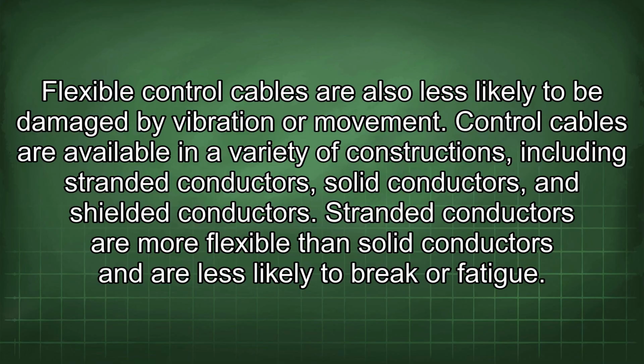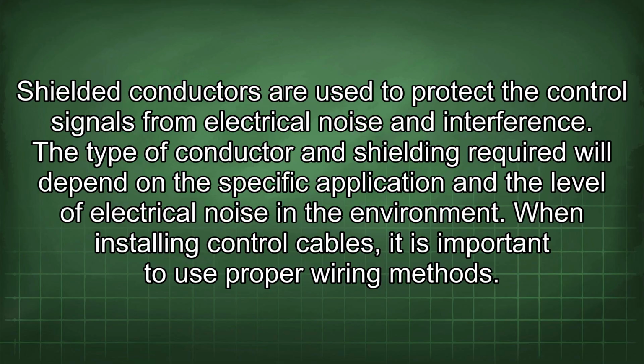Control cables are available in a variety of constructions, including stranded conductors, solid conductors, and shielded conductors. Stranded conductors are more flexible than solid conductors and are less likely to break or fatigue. Shielded conductors are used to protect the control signals from electrical noise and interference. The type of conductor and shielding required will depend on the specific application and the level of electrical noise in the environment. When installing control cables, it is important to use proper wiring methods.